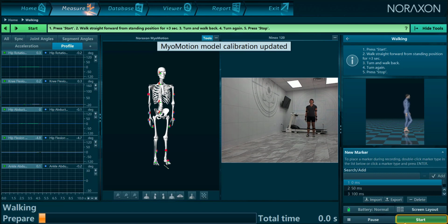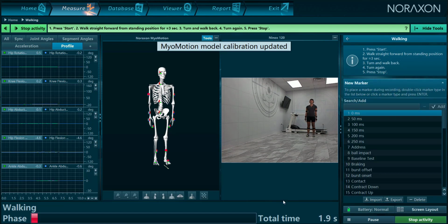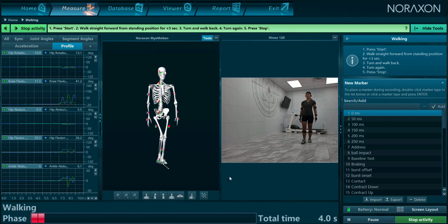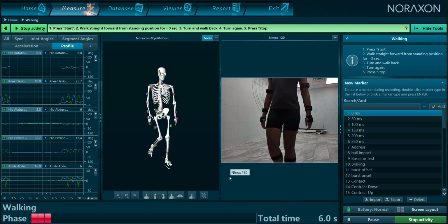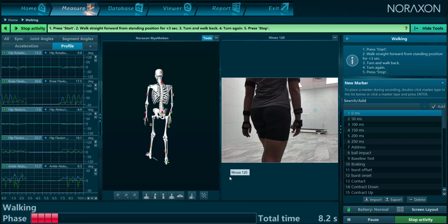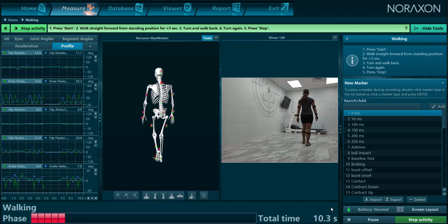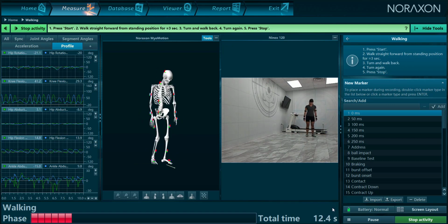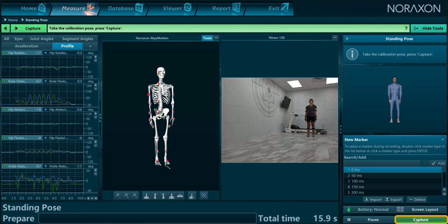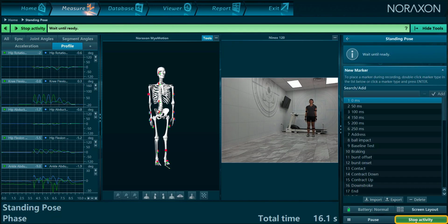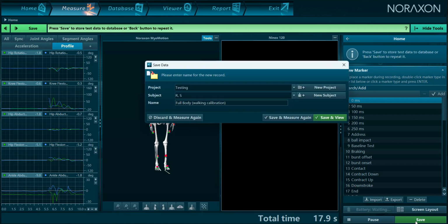Select Start, then instruct your subject to begin walking forward normally and at a normal pace for about 3 seconds, then turn around and walk back. It's important that the subject ends in the same calibration position as they started and in the same spot. Once in place, select Stop Activity. After this, the standing pose must be captured once more. To store the calibration and apply it to the next measurement, select Save and Measure again.